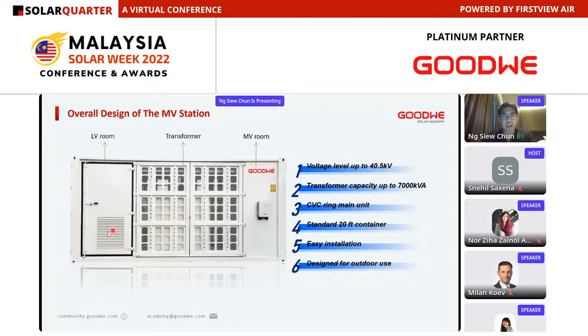So again, I think this is the overview of our MV station. It's an LV room and an MV room. The LV room would be the 800 VAC, and it can connect up to 28 units of inverters, ACCB, and so on. And the MV room is up to 11 kV or 33 kV by project design.